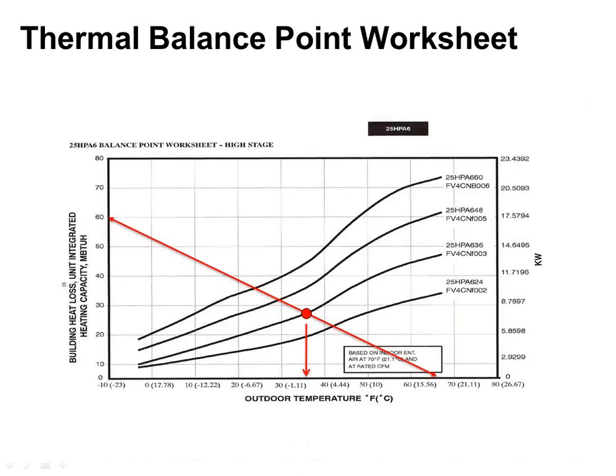So on the bottom of this chart, you have the outdoor temperatures going on the bottom from minus 10 to 80 on the chart, and you have your building heat loss, your load, going from 0 to 80,000 BTUs at the left-hand side. And then on this particular chart, I have 4 different heat pump combinations mapped on here. The bottom one's a 2-ton, 3-ton, 4-ton, and a 5-ton cooling heat pump on here. And each one of them has their curve, and you can see as it gets colder outside, they drop off. It's not necessarily a straight line because the airflows are changing and things like that.